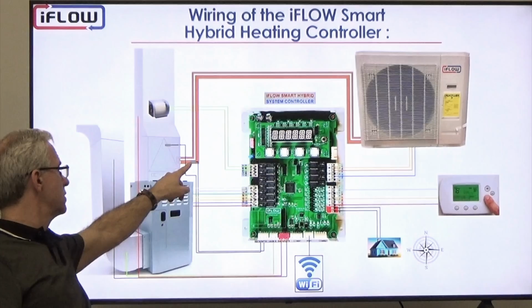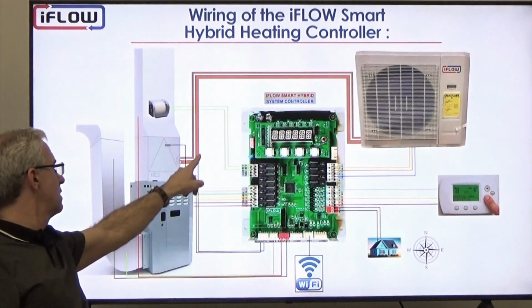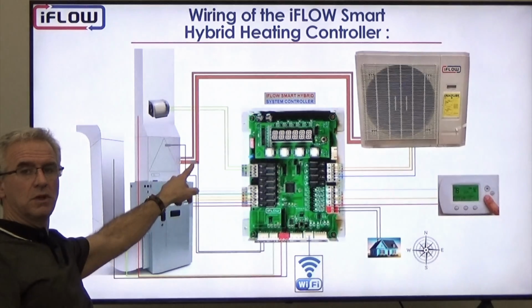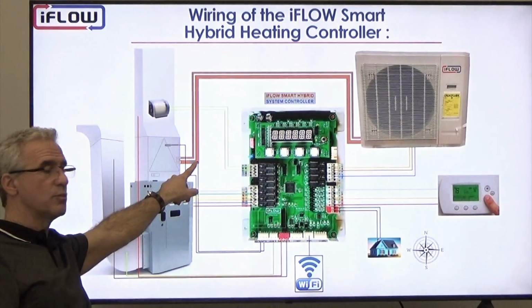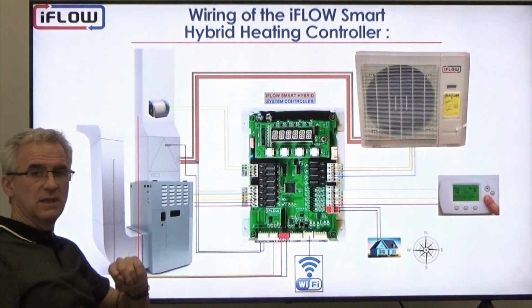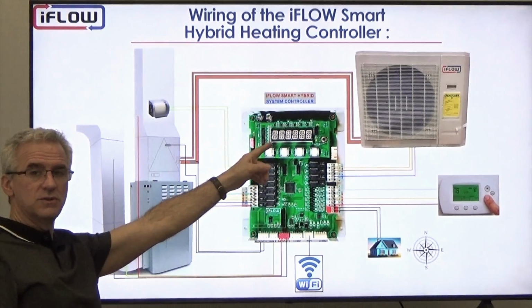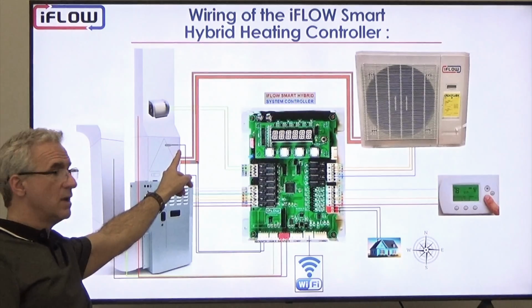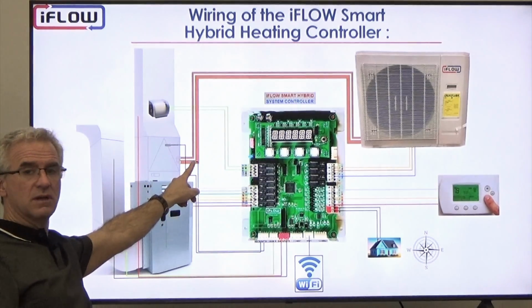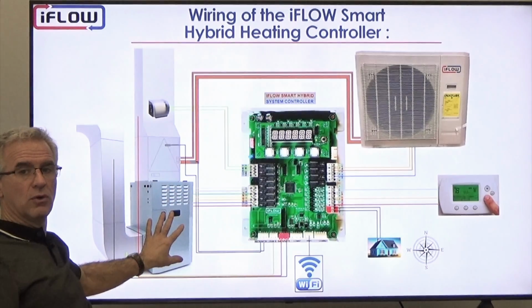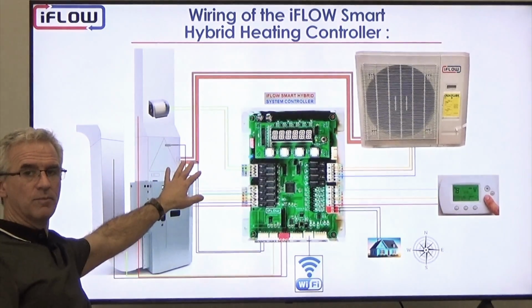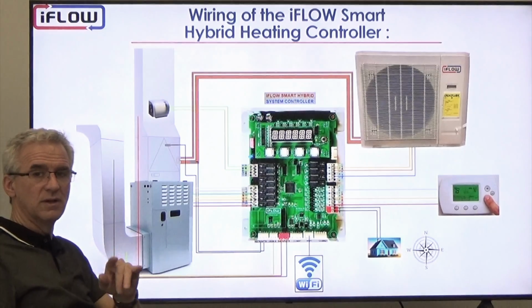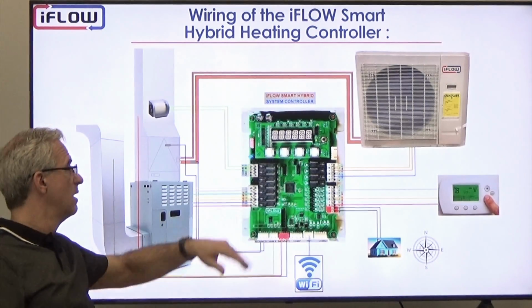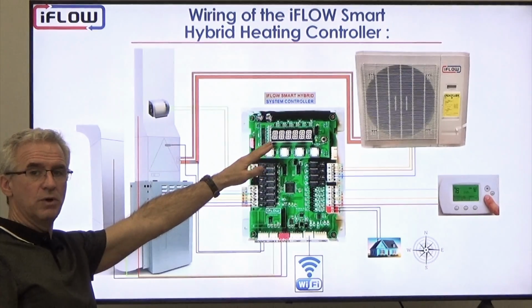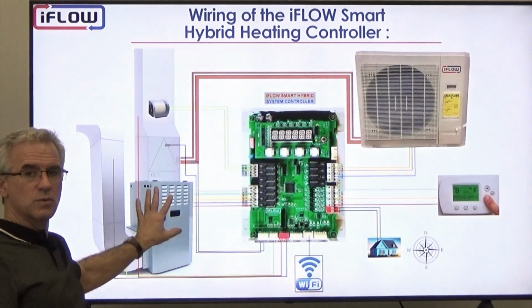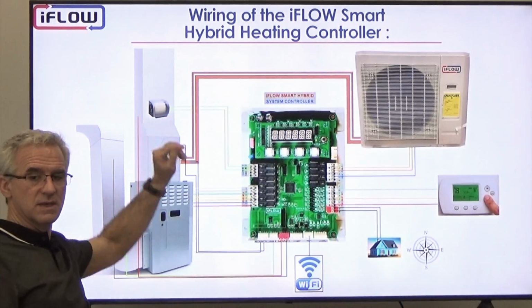This sensor will strap to the suction line from the compressor in the mechanical room, probably 8 to 10 inches away from the evaporator. That sensor is going to tell us what temperature the outdoor unit is providing to the evaporator. And again, once it goes over 90 degrees on a heating call, then we will allow the blower of the furnace to start, not before. We're also looking at the time. How long does it take to get that? If it's more than 20 minutes, then we switch. Even though we've got a call from the heat pump, we'll say something's wrong with the heat pump and we'll switch over to the furnace, so the homeowner always has heat.